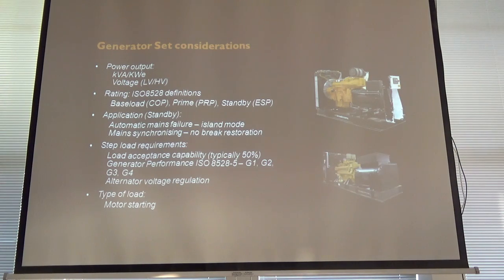The same situation applies. If you're synchronized with a single set or synchronized together, that's exactly what happens when the engine alternator sees the load. The fuel rack will open up, depending on how aggressive it is and what the parameters are, pedal to the metal to overcome that load step, that hill that's just been applied. When the set's been running along, it doesn't necessarily see that coming, so it has to react very, very quickly.